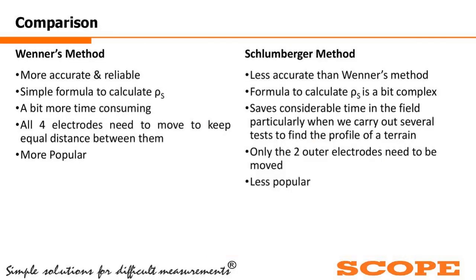Then we will come to the comparison, as I have already covered some of the points here. Wenner's method is more accurate and reliable. Schlumberger method is not as accurate as Wenner's method. Wenner's method has a simple formula, whereas the formula in Schlumberger method is a bit complex. Wenner's method is a bit more time consuming, but Schlumberger method is not that time consuming, because it saves considerable time in the field, particularly when we carry out several tests to find out the profile of a terrain, because only the 2 outer electrodes are moved. We are not moving the entire setup, because once we have fixed the inner 2 voltage probes, we can keep them fixed and keep on changing only the outer 2 probes.